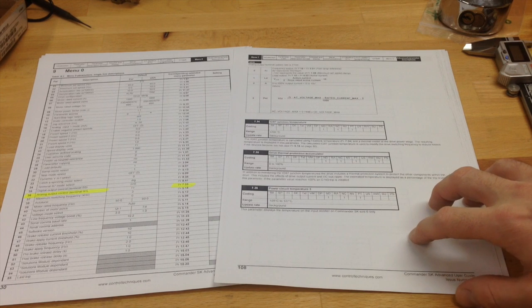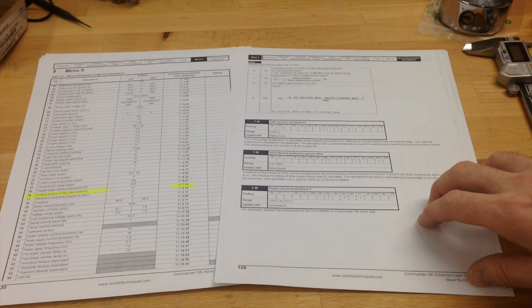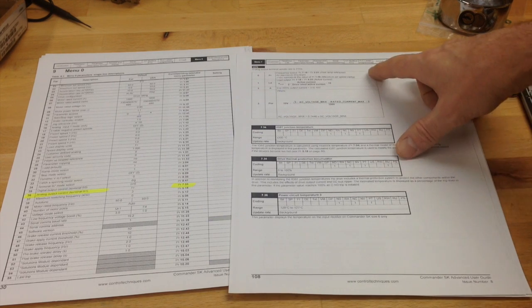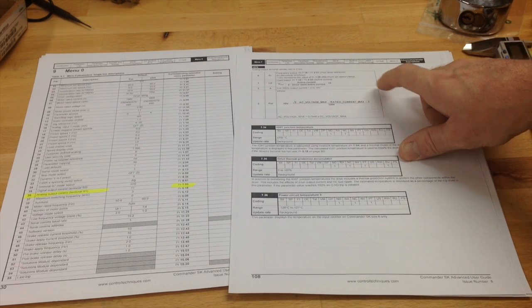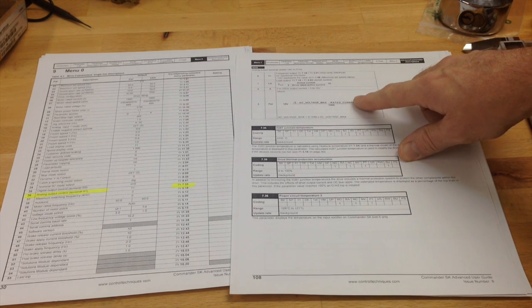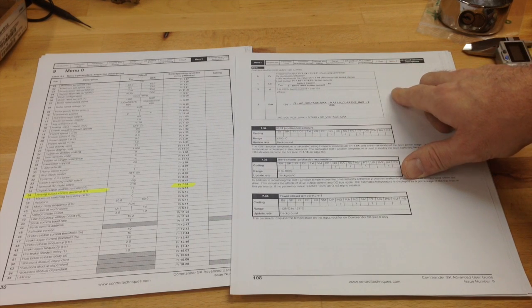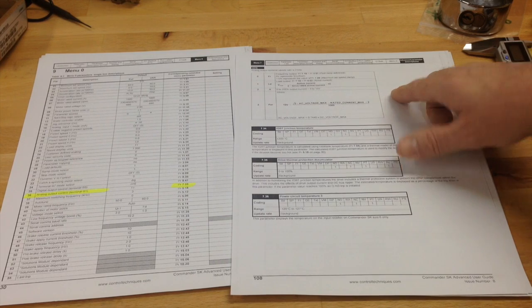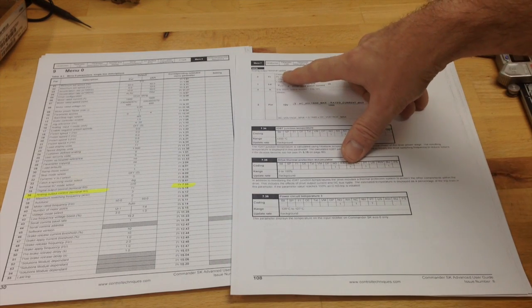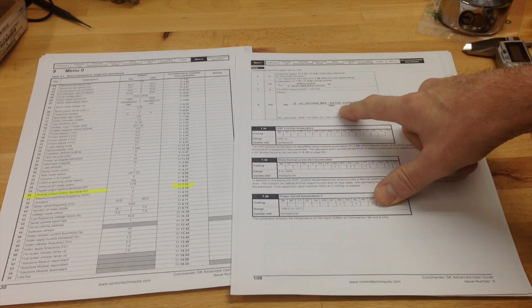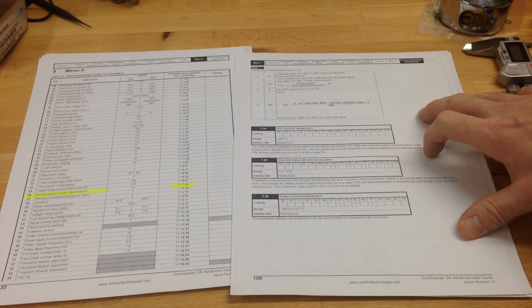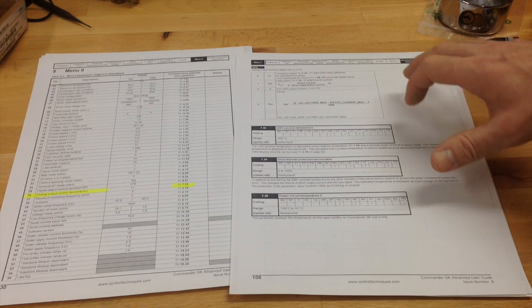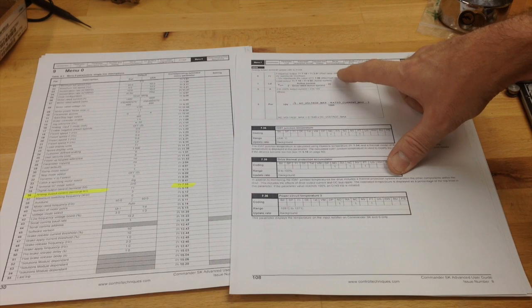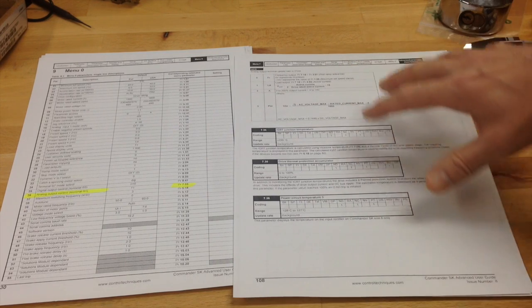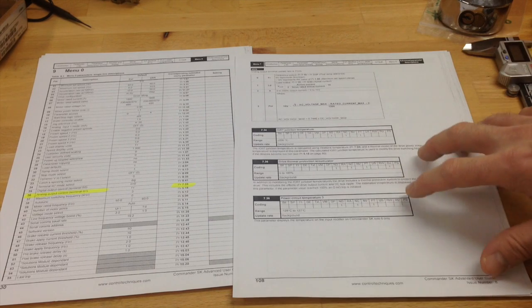And particularly, we're after this sort of extended parameter of 7.33. You can see here there's some mathematical formulas of how it uses some of the parameters that it's calculated internally, does some math with them, and outputs a reference voltage on the analog output pin from the VFD. There's four choices: frequency, load, current, and power. In general, this reference voltage is a 10 volt signal, but if we use the load option, it'll only ever achieve 5 volts maximum. You can look through the mathematics and read those three pages and you'll understand why.